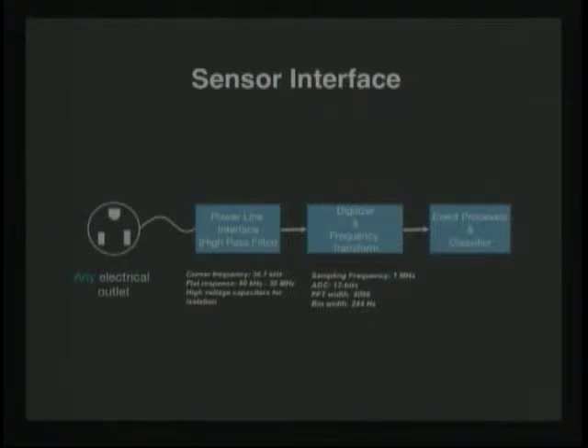So how do we sense this? The sensor is actually pretty simple. It's basically a physical connection to the power line. It looks like a little box that plugs into an outlet. There's a high-pass filter, which has a corner frequency of 36.7 kilohertz. The key here is you've got to knock out all the 60 hertz, because we're looking at the high-frequency noise, anywhere from 50 kilohertz up to a megahertz. The filter that we use goes up to 30 megahertz.